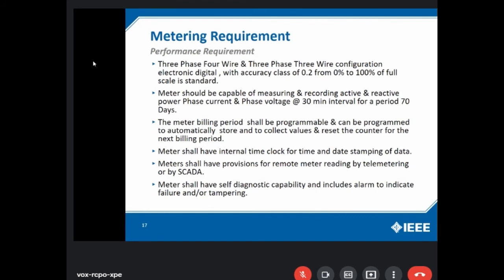Now the performance requirements. Three-phase 4-wire and three-phase 3-wire configuration, electronic digital, with accuracy class of 0.2 from 0% to 100% of the full scale is standard. So 0.2 accuracy class is standard for metering purposes. Meters shall be capable of measuring and recording active and reactive power, phase currents, and phase voltage at 30-minute interval for a period of 70 days.